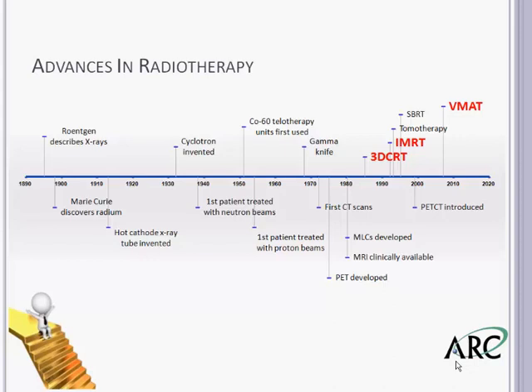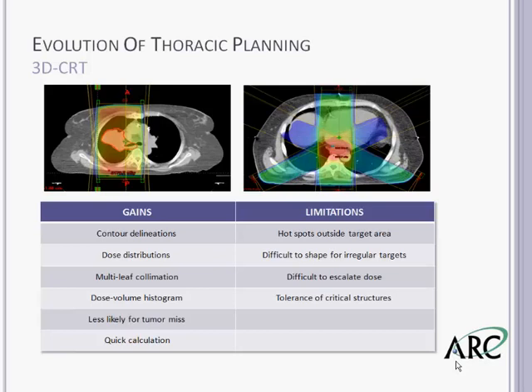Given all these advances, we'll be talking specifically about the thoracic region and the modern perspectives of 3D, IMRT, and VMAT. The move from 2D to 3D in the 1980s was a major advance because it took into account axial anatomy and complex tissue contours such as the hourglass shape of the neck and shoulders. We're now able to view 3D images of tumors and normal structures, and create reliable dose distributions. Beam's eye view technology — in which the beam is shaped from multiple angles using MLCs — allows for evaluation of treated doses as a function of dose and volume, called a dose-volume histogram.